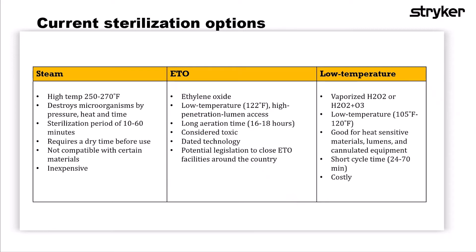ETO has been utilized for a very long time. A fun fact is that ETO was utilized as early as World War I and II for sterilization of meal rations. It is classified as low temperature and has high penetration of lumen accesses. It also has a very long aeration time because the chemicals used in ETO are carcinogenic and must be vented out over a long period of time to be safe for both humans and the environment.